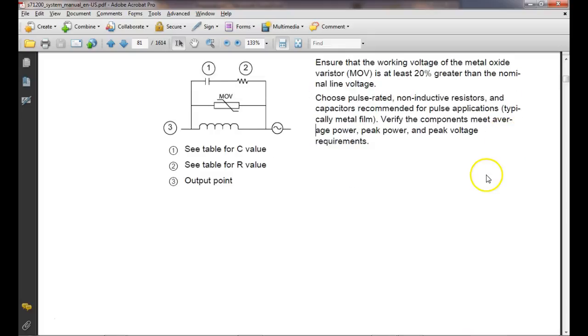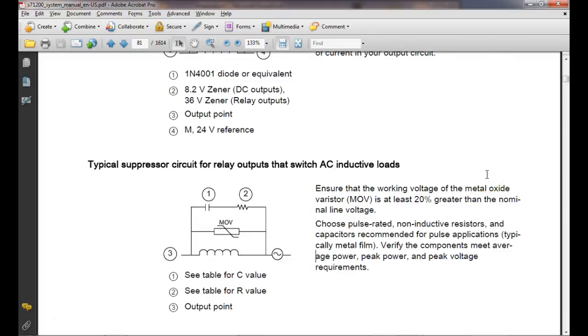We're not going to have to worry about it here because all these suppression devices are already on our coils for us, right? But if you get the privilege of actually wiring up the whole PLC circuit, some of y'all might get into that, then you're going to have to remember to put those suppression devices on these relay coils, because that's what they do - they suppress that counter EMF.